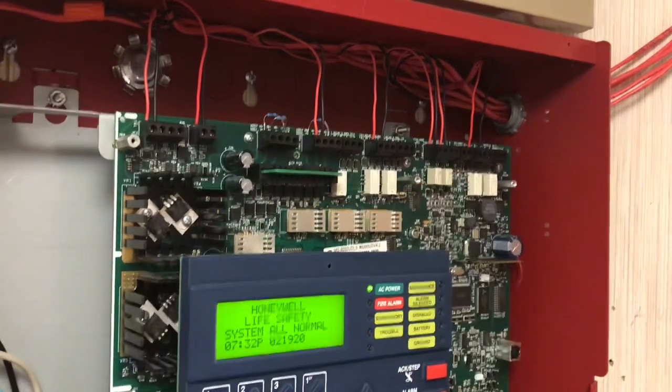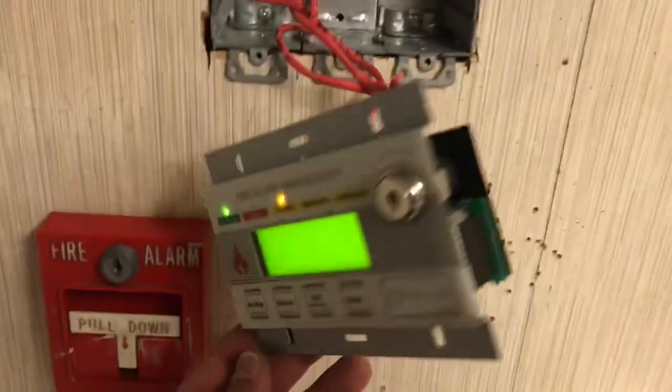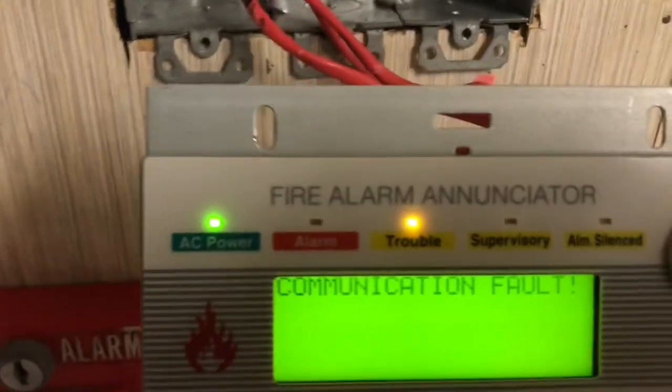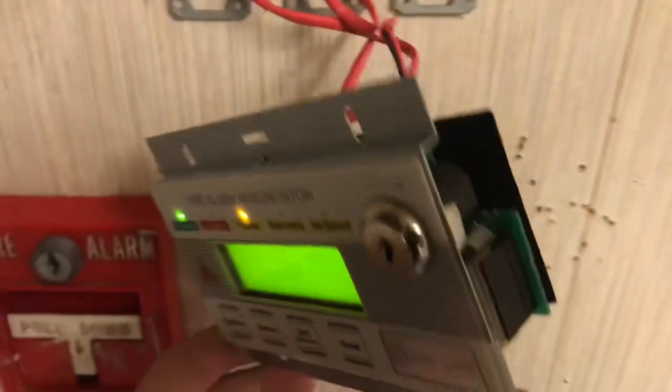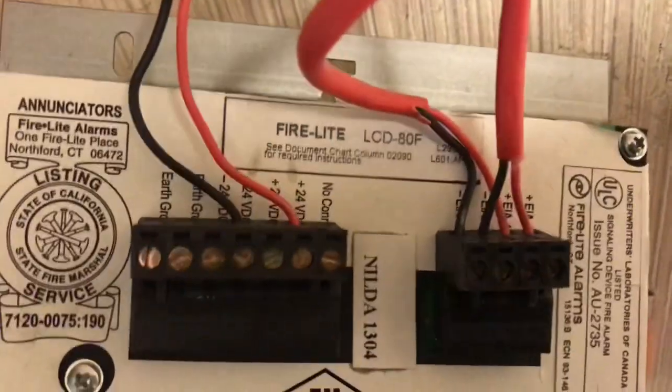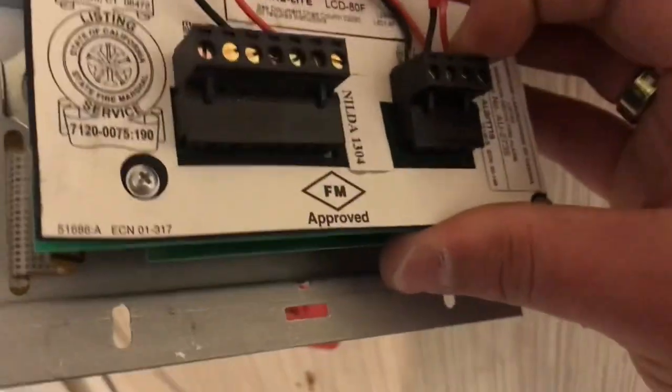Now I'm going to show you how the annunciator gets wired. I took it out of the wall to show you — right now it says 'communication fault.' It has 24 volt power but it's not programmed into the system yet. Here's the back of it: there's your 24 volt power — positive and negative — and here are the communication lines. You can unplug them and plug them back in when wiring.